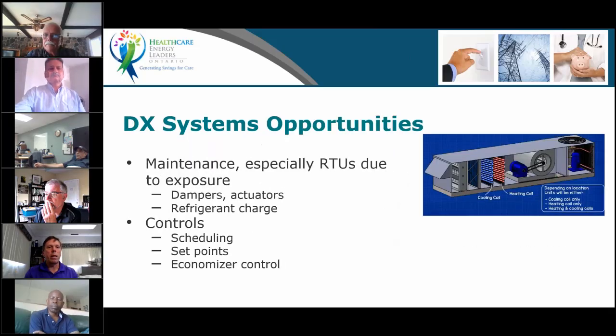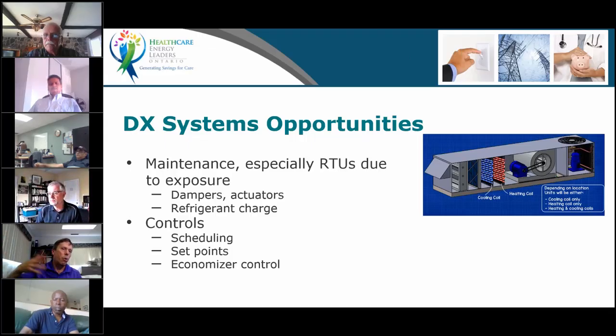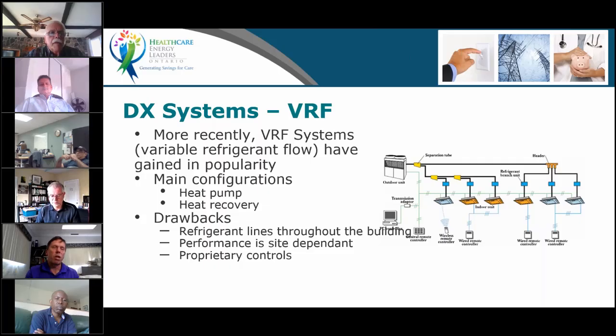For those rooftop units, DX systems, they're often forgotten in terms of maintenance. They're on the roof. You go there and the dampers are not very good. Economizer may not be working. They may not have been centralized for some reason, depending on the OEM control that was on there. So always keep on top of that when we're talking about cooling. Make sure the economizer is working on those and that the set points are properly set, especially when they have not been centralized.